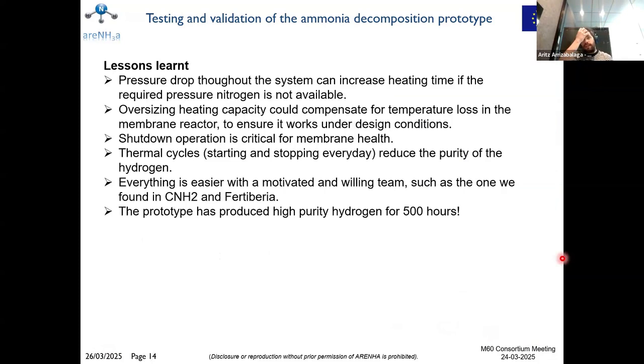So, several lessons learned: we didn't quite know where this was going to be installed or under what conditions it would work, but we need to be less optimistic when it comes to pressure drop or heating capacity, because that has a big impact on performance. We need to be more conservative in these calculations so the system can work across a wider range of operating conditions.